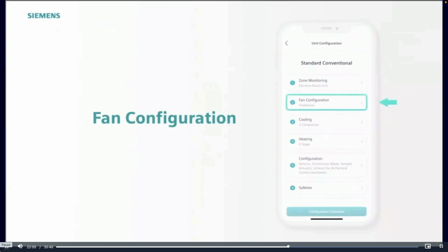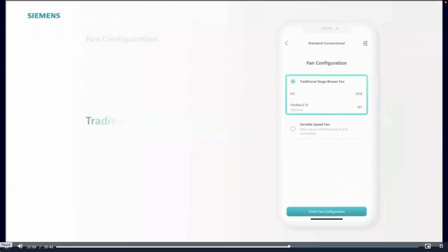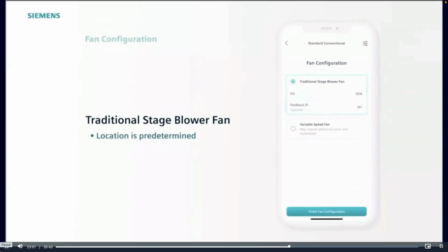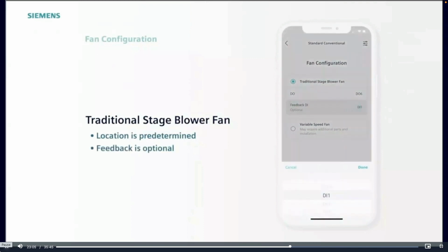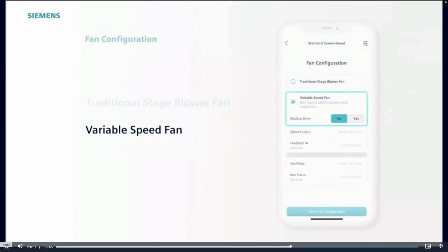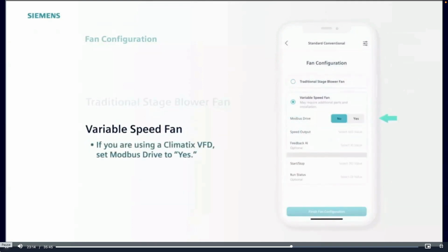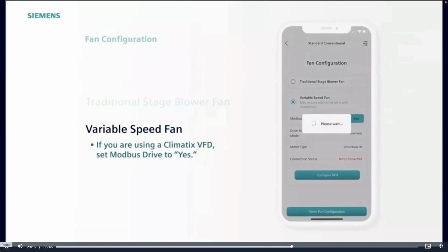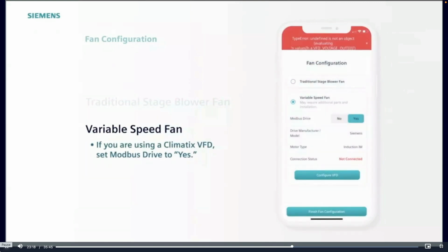Next, select fan configuration. If you've selected traditional stage blower fan, it is predetermined on DO6, with the optional fan feedback on DI1. As the feedback is optional, simply tap it, choose none if you do not need it. If you've selected variable speed fan and you use a Climatix VFD, select yes for Modbus drive. You'll notice this example showed an error because we are not connected during this demonstration. You should not see an error when connected.